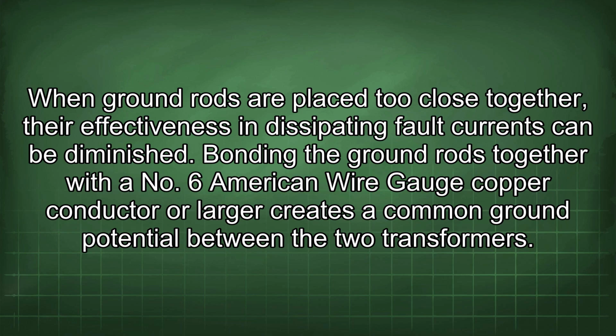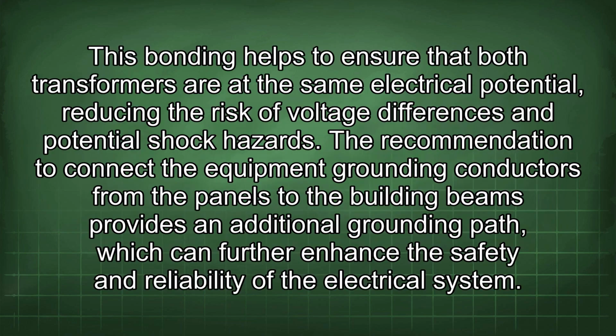Bonding the ground rods together with a number 6 American wire gauge copper conductor or larger creates a common ground potential between the two transformers. This bonding helps to ensure that both transformers are at the same electrical potential, reducing the risk of voltage differences and potential shock hazards. The recommendation to connect the equipment grounding conductors from the panels to the building beams provides an additional grounding path, which can further enhance the safety and reliability of the electrical system.